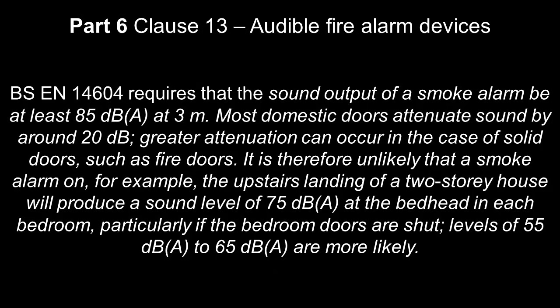So in domestic is a little bit different. So BS EN 14604, which is the product standard for domestic smoke alarms, requires that the sound output of a smoke alarm may be at least 85 dB at 3 meters. So all these detectors are designed so that at 3 meters, the sound level reading will be 85 dB. Hence the previous statement saying that a smoke detector has to be within 3 meters of a bedroom door.